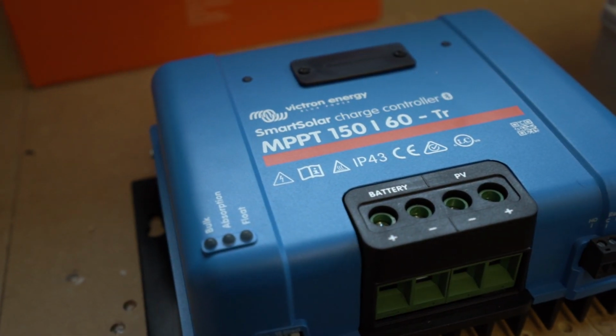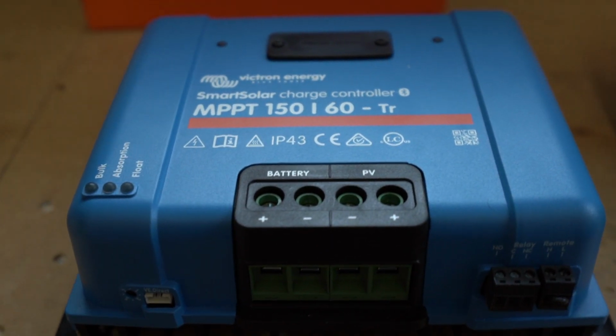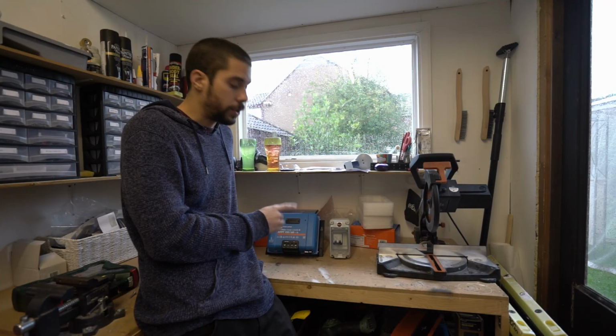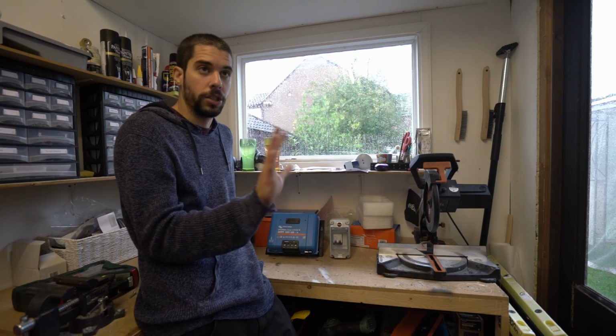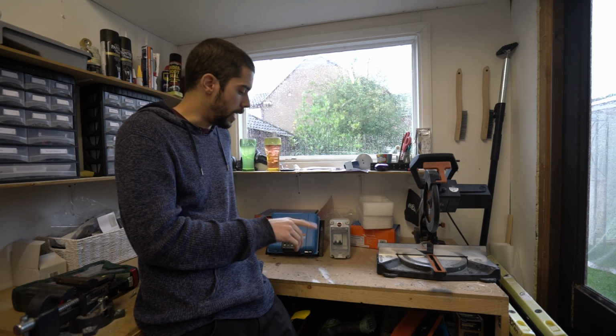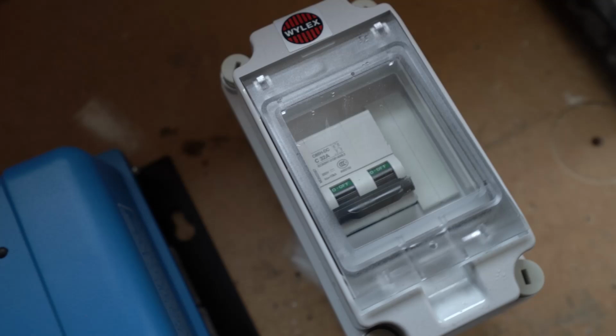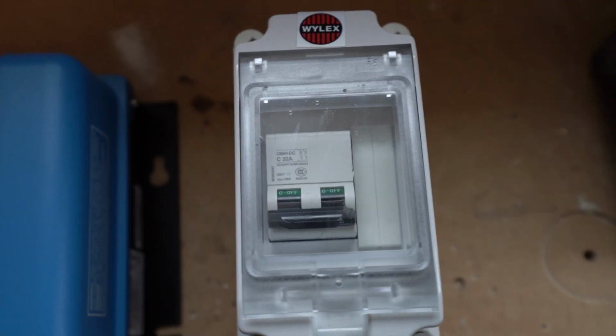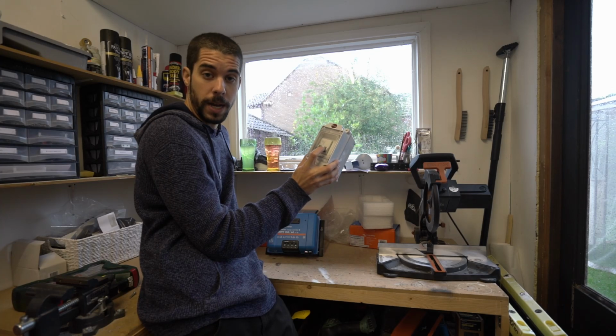The MPPT we're going for is the Victron 150/60. TR Smart, and we're going for this cutoff switch due to space limitations that I will show you next. It's a 32 amp DC breaker inside with 250 volts max.